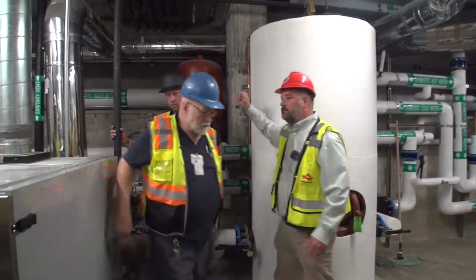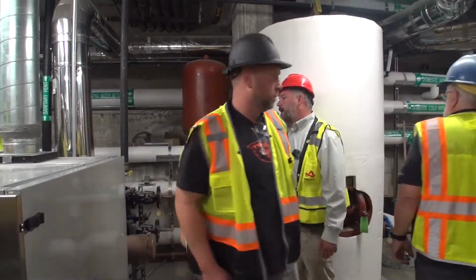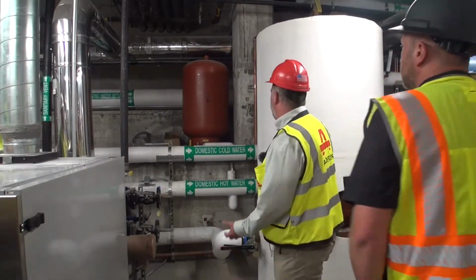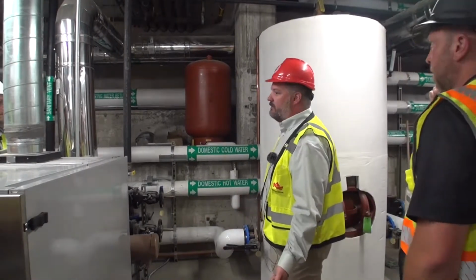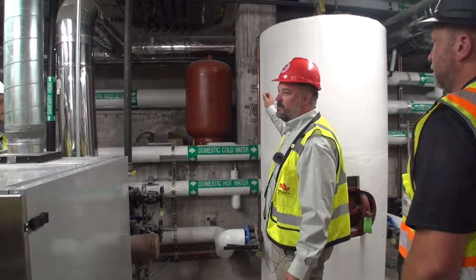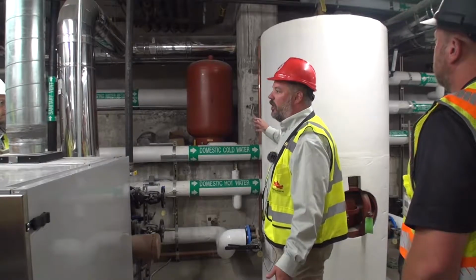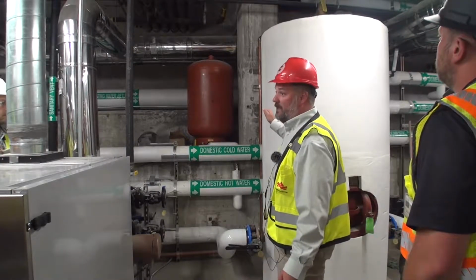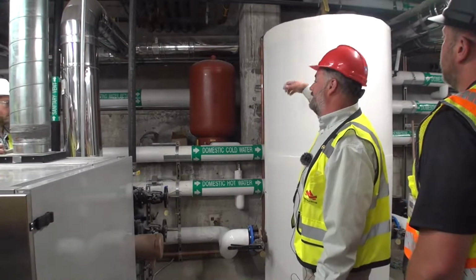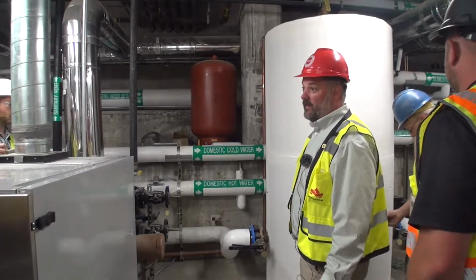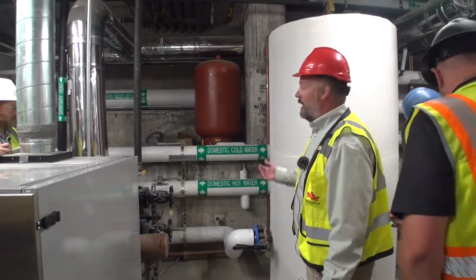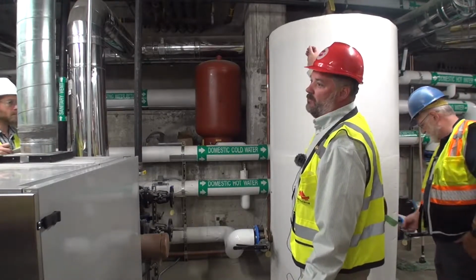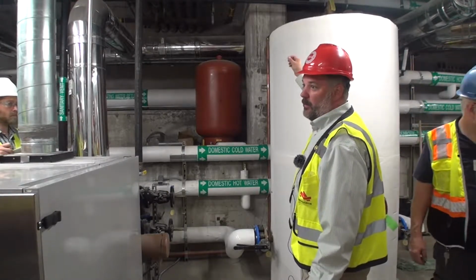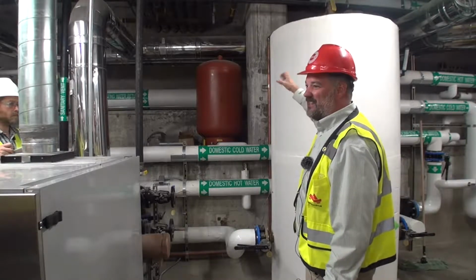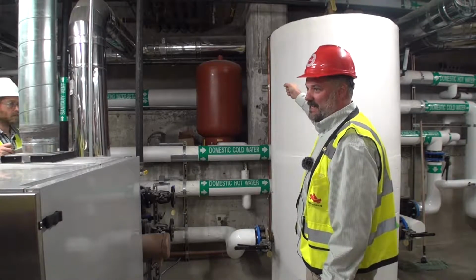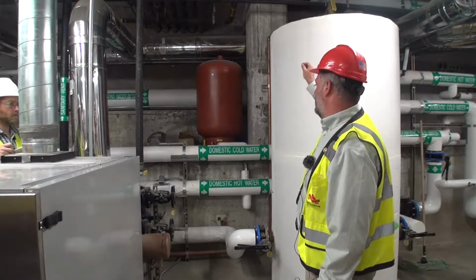Do they need to be tested or used periodically? I get that question. You can exercise them if you want. The problem is a lot of times when you exercise them, sometimes you can't get them back to seat properly. So if they relieve, traditionally we do say to replace them so that the seating can come back to normal. But they will fail and relieve if we've got a weak spring, so you don't really have to exercise it to actually get there. It's not like they're going to stick closed. They will fail open.